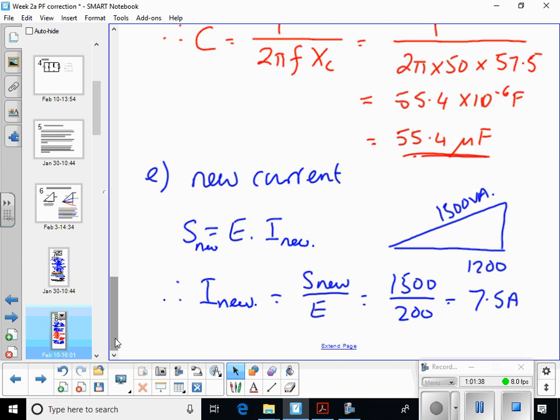You don't want to put too much in because that becomes too costly. But you can see that if your reactive load is changing, with motors starting up and stopping, like big compressors, they used to have compressors with 100 horse motors, starting and stopping, you want to be able to react to that, because your power factor is going to be going up and down, and therefore you want to switch capacitance in and out. But you're never going to hold it. It's not infinitely variable. It's done in steps, to try and keep it within a band. And 0.8, 0.9 is what's aimed for usually.